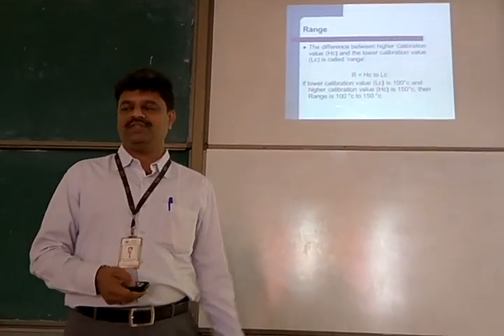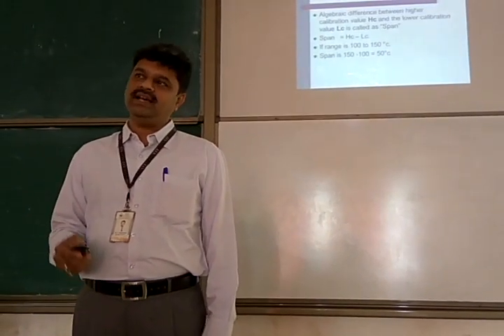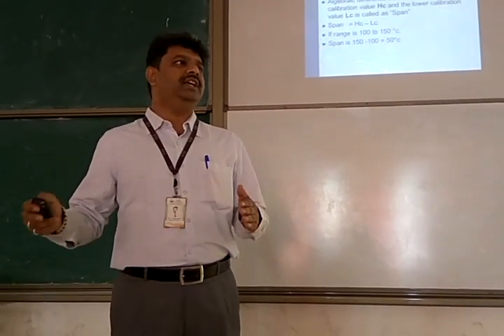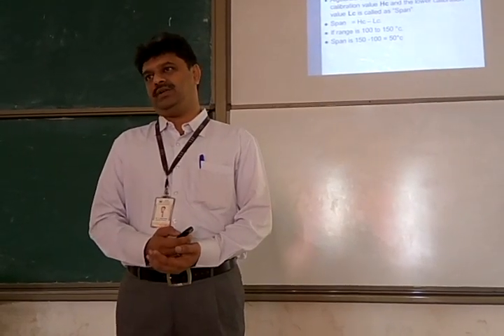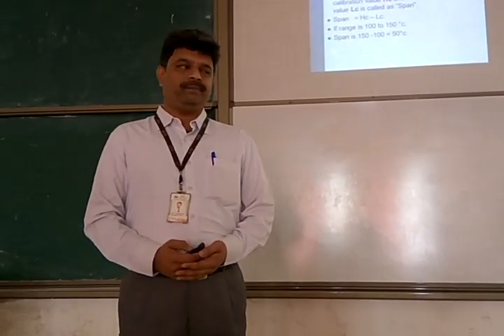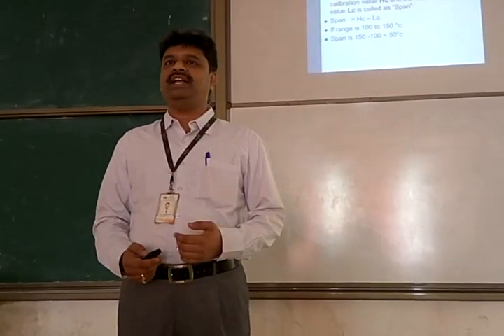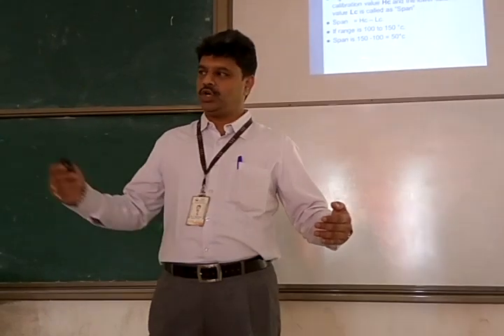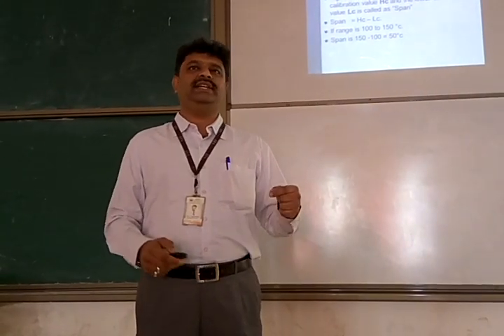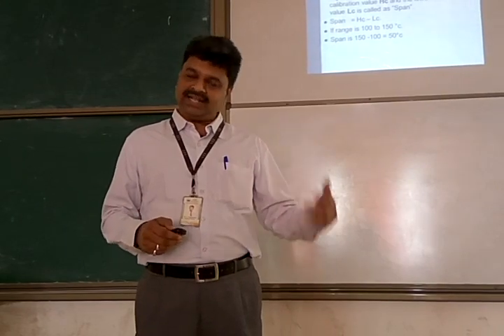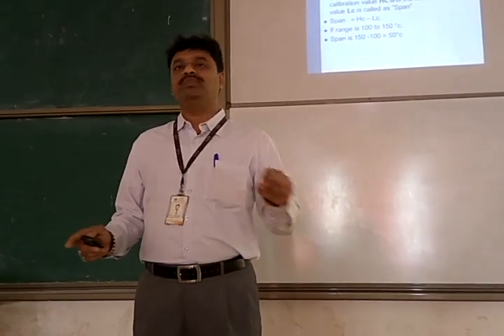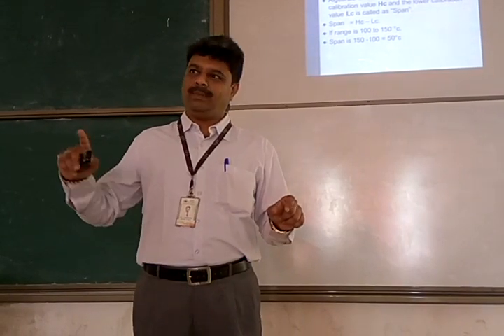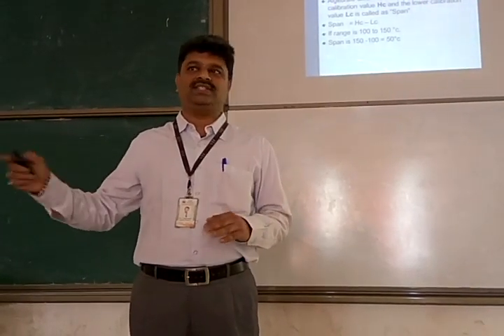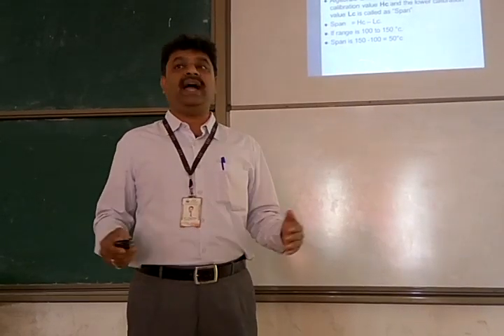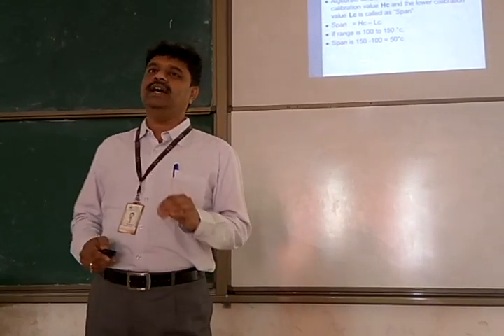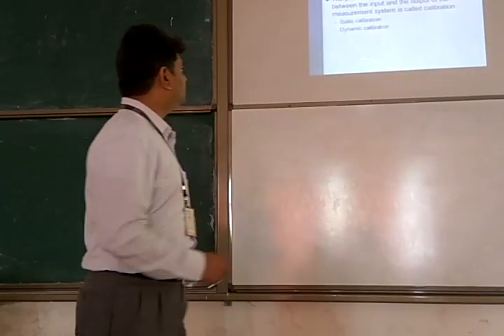Range is from the lower calibration value to the higher calibration value, and span is the algebraic difference between the lower calibration value and the higher calibration value. What is meant by algebraic difference? If the instrument is capable of reading from minus 40 degrees Celsius to 300 degrees Celsius, the range is minus 40 degrees Celsius to 300 degrees Celsius, whereas the span is 300 minus minus 40, so it is 340 degrees Celsius. That is the span of the instrument. Okay? So there is a difference between range and span that you have to be clear about.